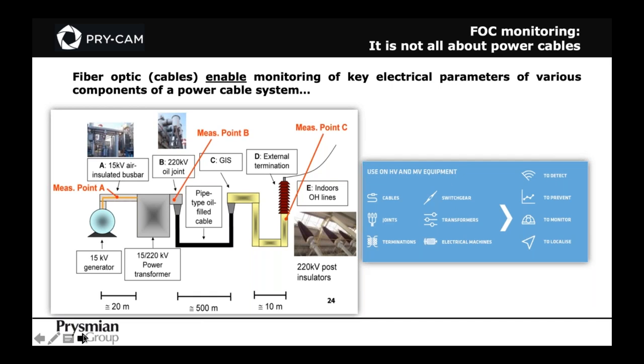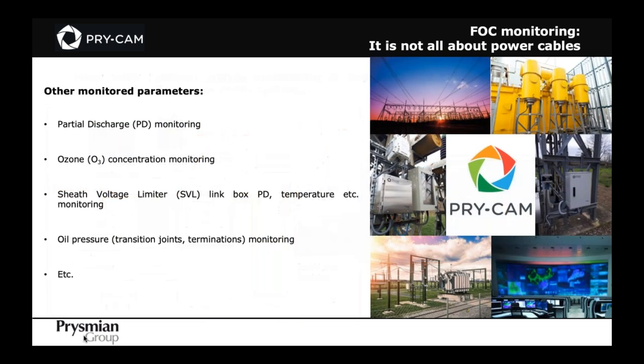Parameters that we look for using fiber optics, in some ways, are partial discharge, ozone concentration in switchgear cabinets, for instance, PD, temperature, voltage, current for link boxes in high voltage underground transmission systems, and oil pressure for transition joints and terminations. So a lot of things can be done using fiber optics.